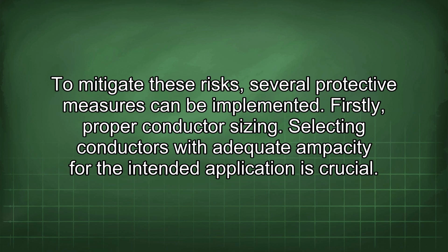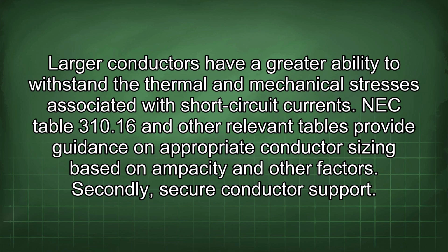To mitigate these risks, several protective measures can be implemented. Firstly, proper conductor sizing. Selecting conductors with adequate ampacity for the intended application is crucial. Larger conductors have a greater ability to withstand the thermal and mechanical stresses associated with short-circuit currents. NEC Table 310.16 and other relevant tables provide guidance on appropriate conductor sizing based on ampacity and other factors.